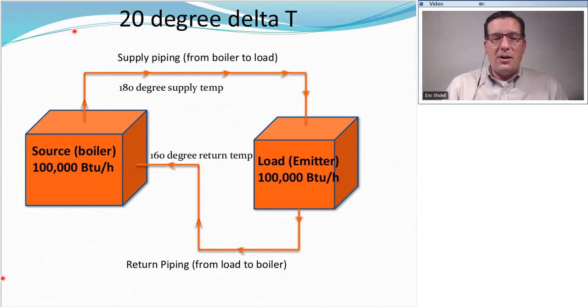Okay, so last thing I want to talk about is what we call the 20 degree delta T. Like I said earlier, delta T means difference in temperature. And a lot of our hydronic heating systems are designed around and meant to operate based on a 20 degree temperature difference. And this is true on both the boiler side and it's true on the returns, or on the system side, on the load side or the emitter side. As water passes through the boiler, it should rise in temperature 20 degrees. This gives us the most effective transmission of energy from the flame into the passing water and avoids some problems.